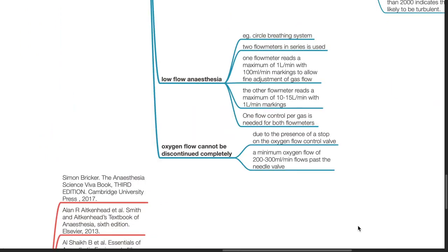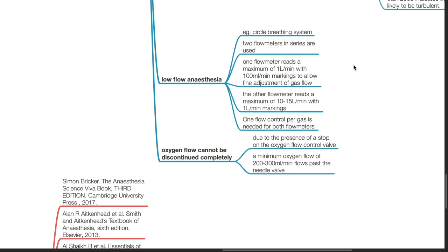Low flow anesthesia, such as in circle breathing systems, two flow meters in series is used. One flow meter reads a maximum of one liter per minute with 100 mls per minute markings to allow fine adjustments of gas flow. The other flow meter reads a maximum of 10 to 15 liters per minute with one liter per minute markings.